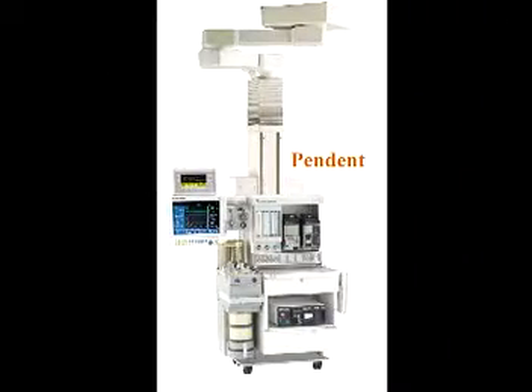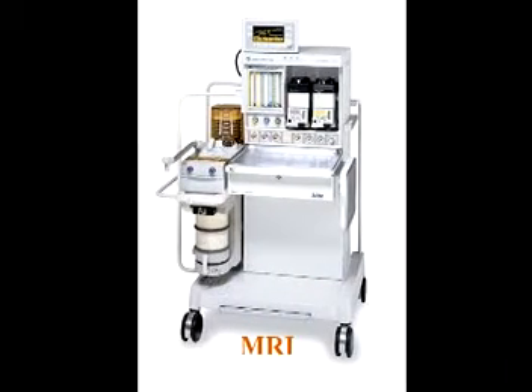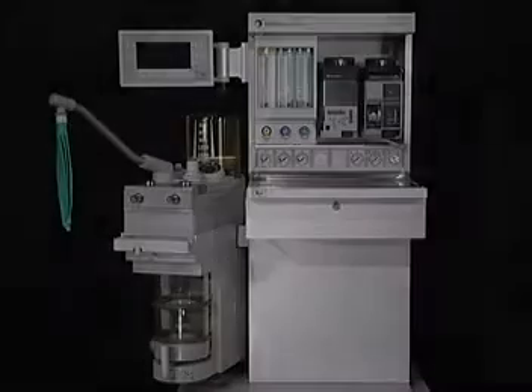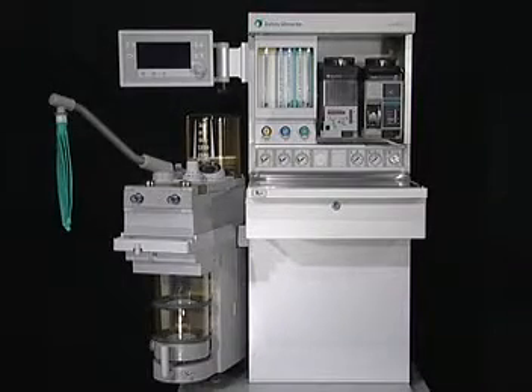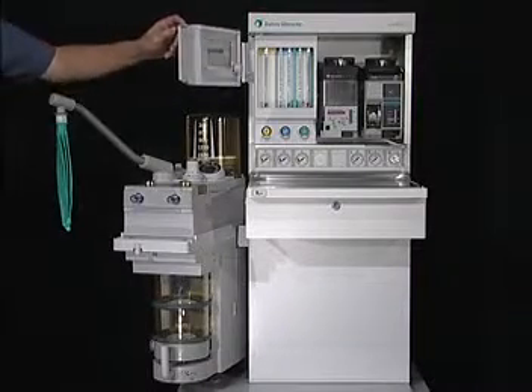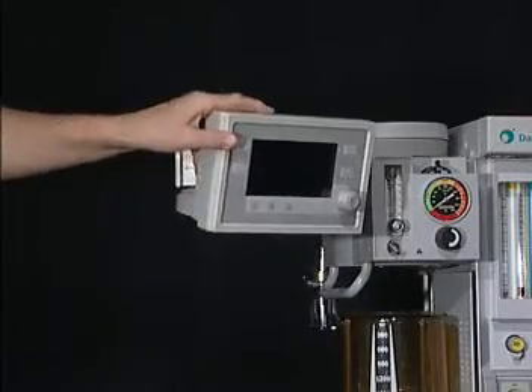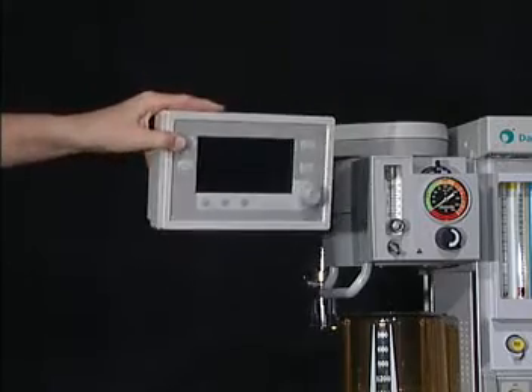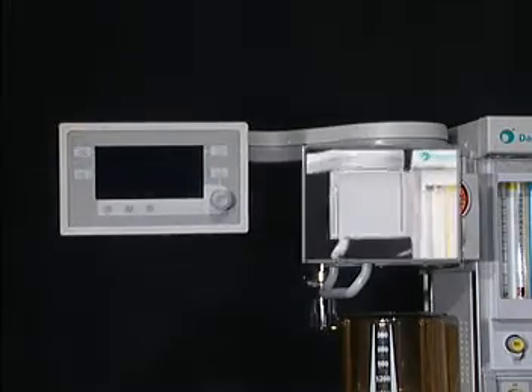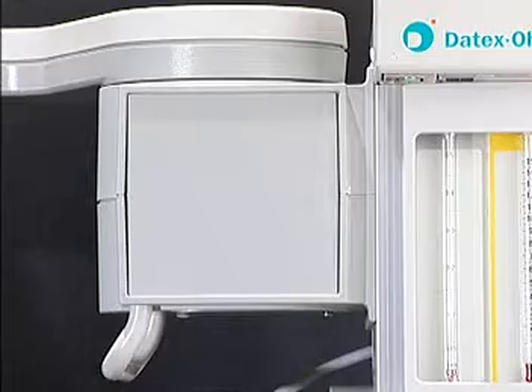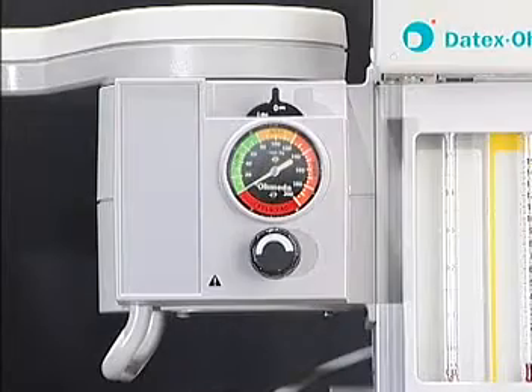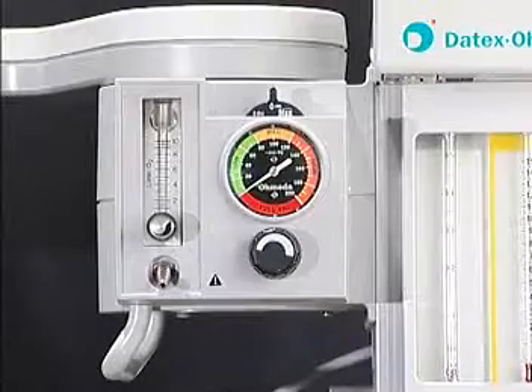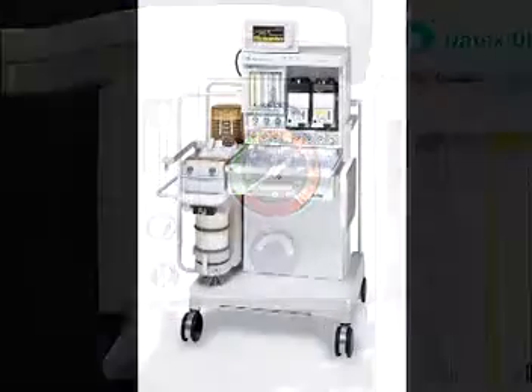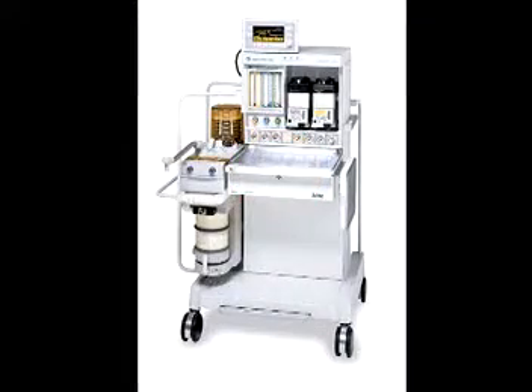Open architectural design offers flexibility for use of many vendors' monitors. Ventilator displays are mounted on a short folding arm located on the patient side of the machine or on an articulating display arm, allowing clinician placement of ventilation data in the position of choice. With this option, we also offer the option of integrated suction and an auxiliary O2 flow meter for use with a nasal cannula. An MRI variant is also available.